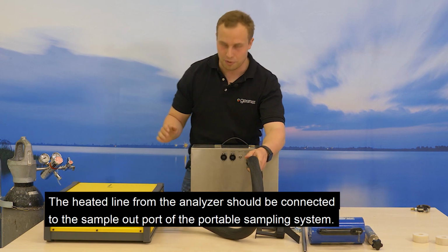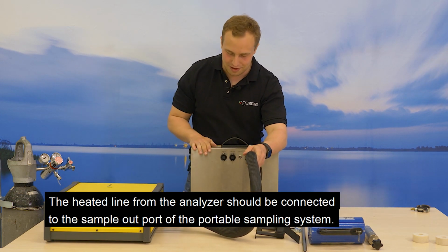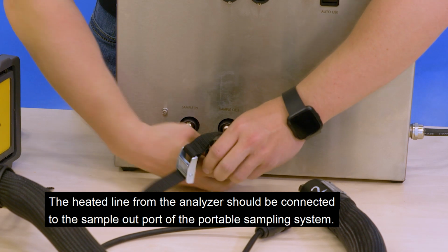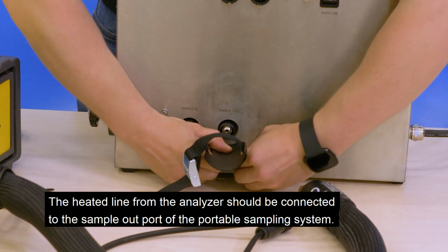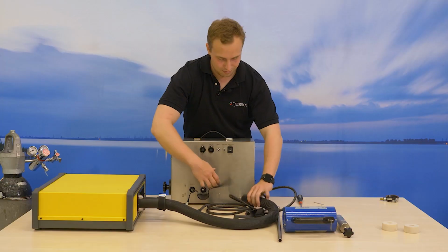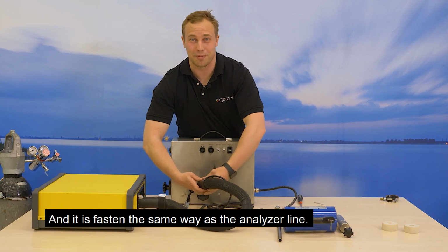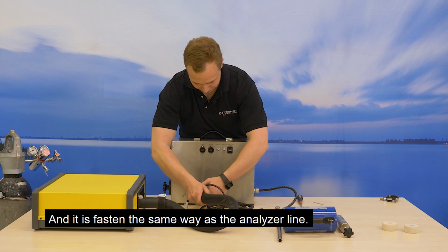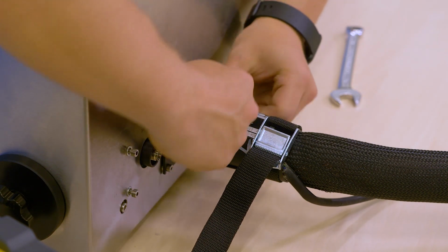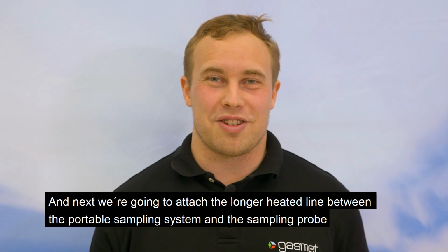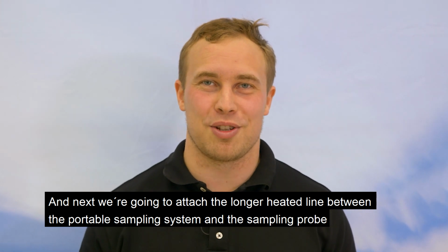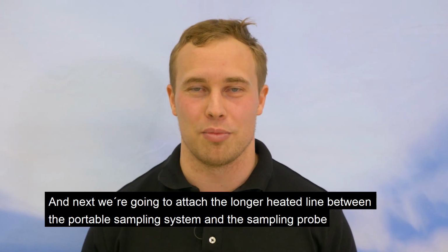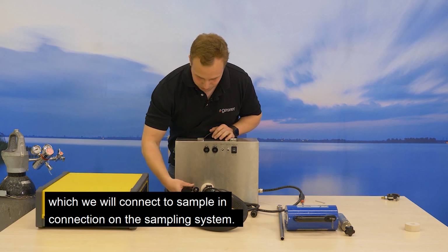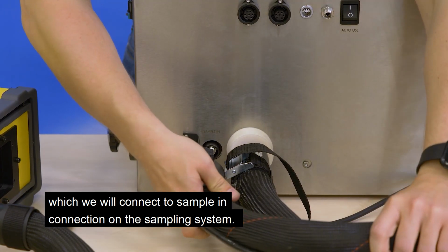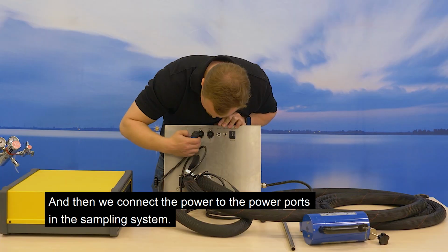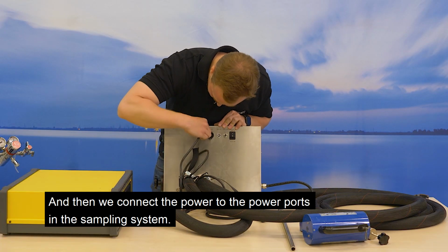The heated line from the analyzer should be connected to the sample out port of the portable sampling system. And it is fastened the same way as the analyzer line. And next, we're going to attach the longer heated line between the portable sampling system and the sampling probe, which we will connect to the sample in connection on the sampling system. And then we connect the power to the power ports in the sampling system.